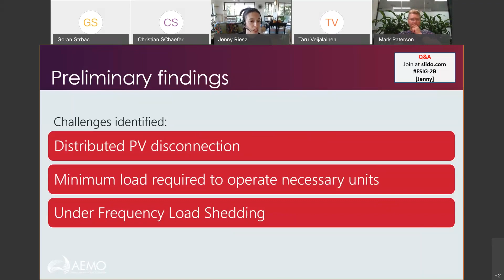So on distributed PV disconnection, this chart is showing you measurements that we've taken from a sample of inverters, based upon data provided by Solar Analytics. Solar Analytics is measuring individual PV systems out in the network, and across a very large sample, thousands of those systems, we're able to look at how they behave when we have major disturbances on the grid. And this chart is showing you the percentage of those PV sites that we observed to disconnect. They suddenly dropped power to zero in response to a voltage disturbance on the transmission network. And the strength of the voltage disturbance is on the horizontal axis, with the most severe events on the right.